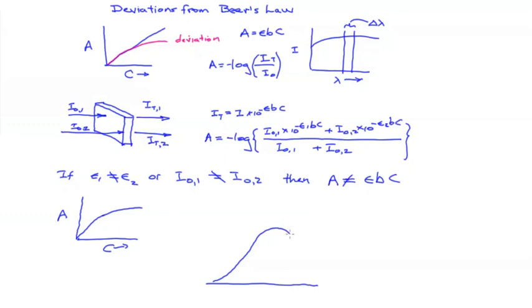When are these conditions going to exist? Imagine that we have an absorption band as a function of wavelength something like this. If the instrument is tuned up on the side of the peak then we get a range of wavelengths that has widely different epsilon values. And that will lead to a non-linear calibration curve.